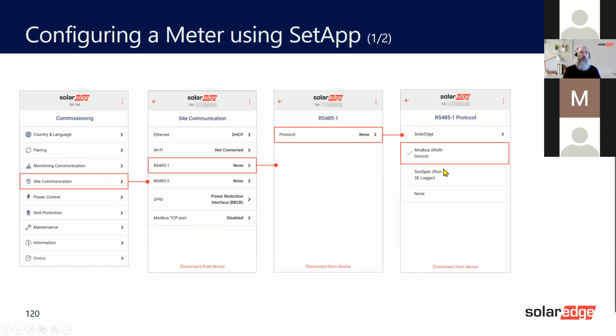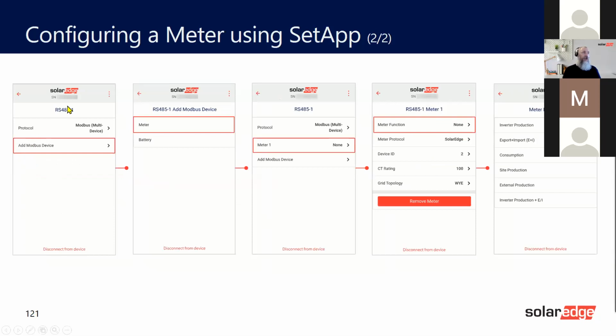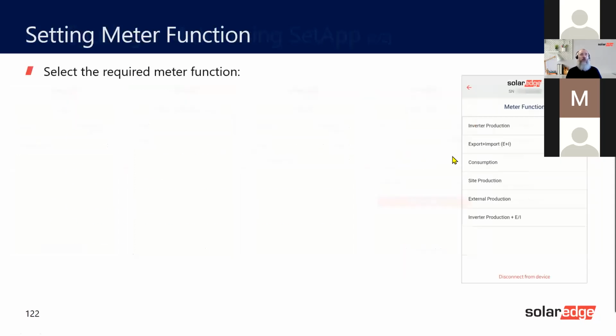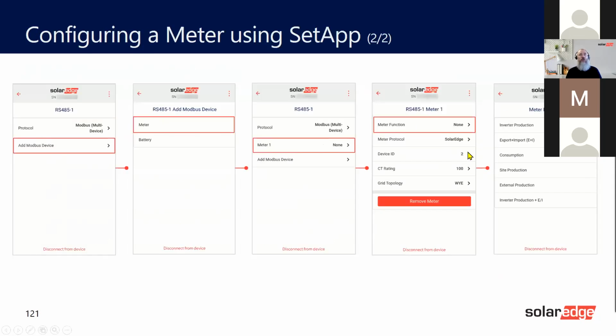You can also do non-SolarEdge loggers as well. Once you get to that stage of multi-devices, then you add a device. You've got a choice of meter or Modbus battery. So you'll go to meter, and then you get meter 1. This is the first one. What you'll notice, because it says meter 1, is that it will say device ID 1. So you'd have to change this to 2. Do you remember how the meter has a dip switch of 2? It was set to ID 2.